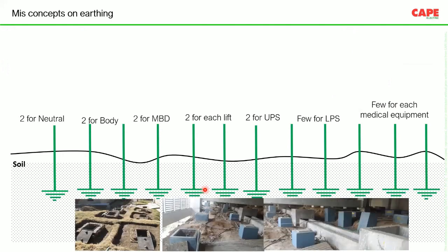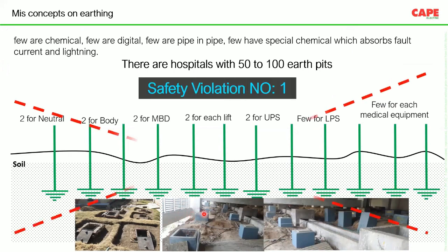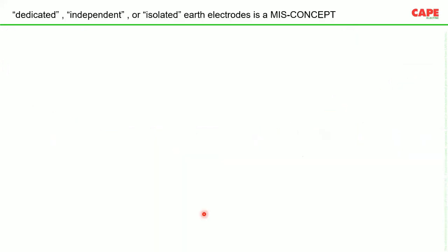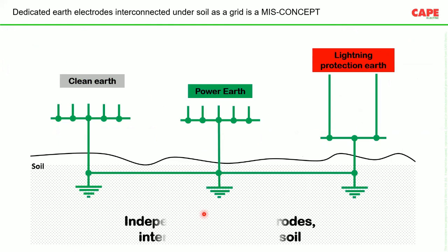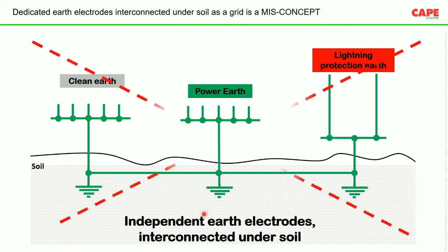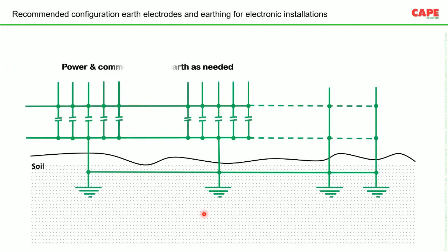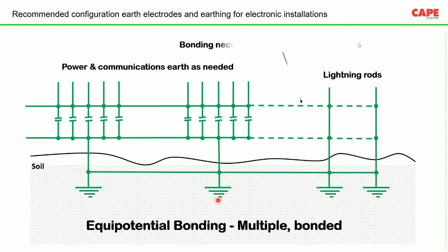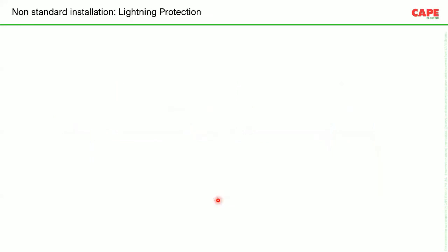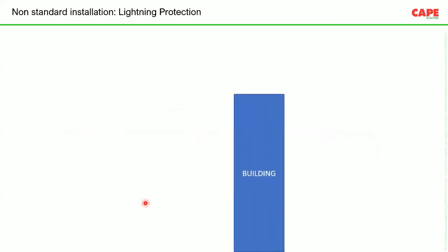Average, if we look all around a hospital, a lot of hospitals have got the earth pit numbers 50 to 100, which is not correct. The correct way of earthing, I just skip these slides. I actually don't want to show that, but unfortunately I forgot to hide it. So the correct way of earthing is protective equipotential bonding. So lightning protection, functional earthing, protective earthing, everything must be interconnected.